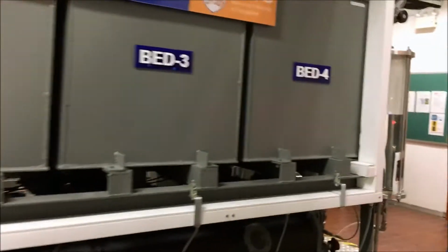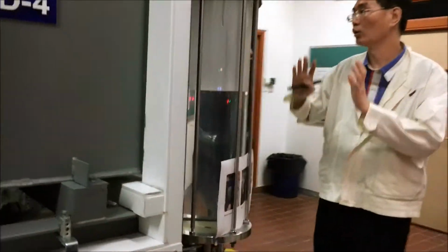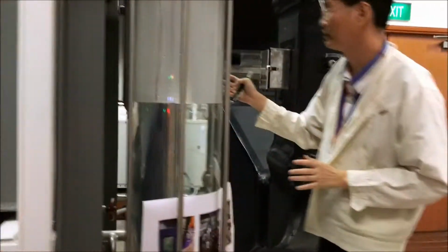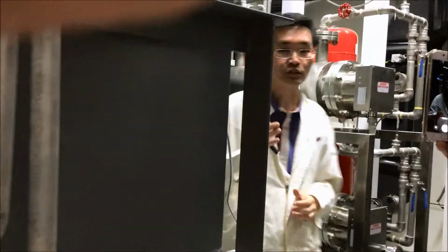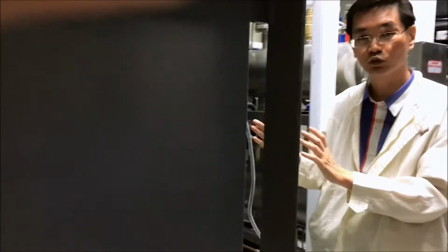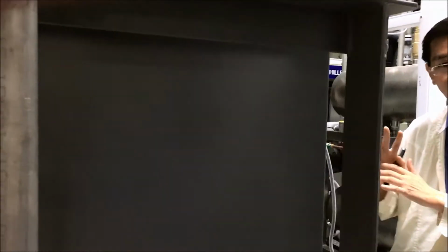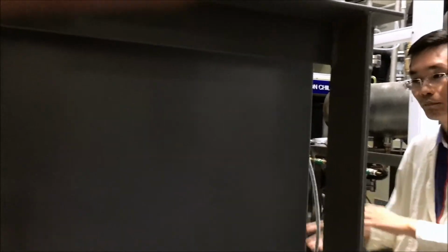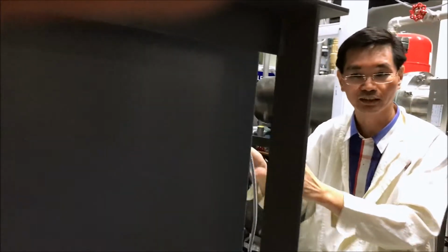So the first stage of the waste heat that comes out will go to the adsorption chiller. The 2-stage adsorption chiller, as you can see from here. This adsorption chiller will produce a chilled water of 6 to 8 degrees, the first stage of chilled water. Coming out from the AD chiller, the temperature is still good, about 70 to 75 degrees, and this will be piped to the AD chiller here, as you can see from here.